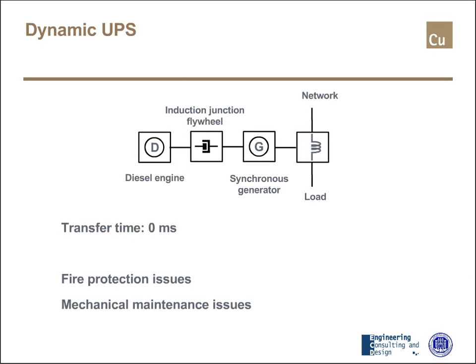Let's spend a few seconds on dynamic UPS and gensets. In a dynamic UPS, energy is provided by a diesel engine — and therefore fuel — and this diesel engine is coupled with an induction junction flywheel to a synchronous generator. The synchronous generator is coupled with the network and the load by way of a large inductance. So the energy is stored in something chemical — in this case fuel, not batteries — and the transfer time is zero, exactly like the double conversion UPS.